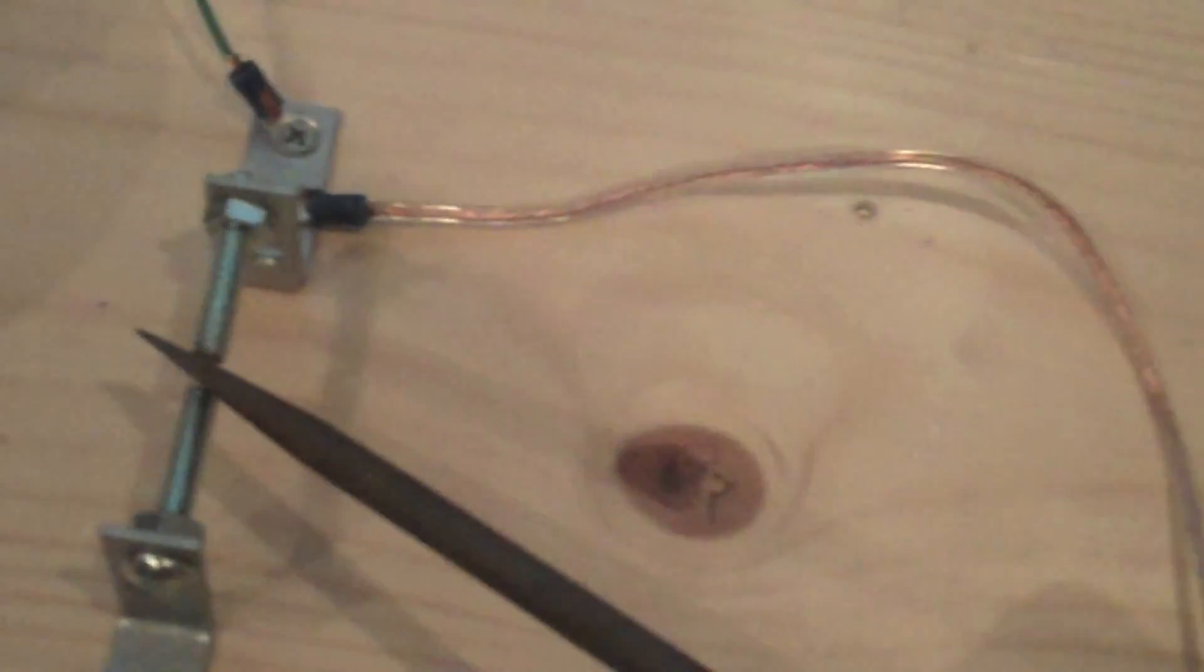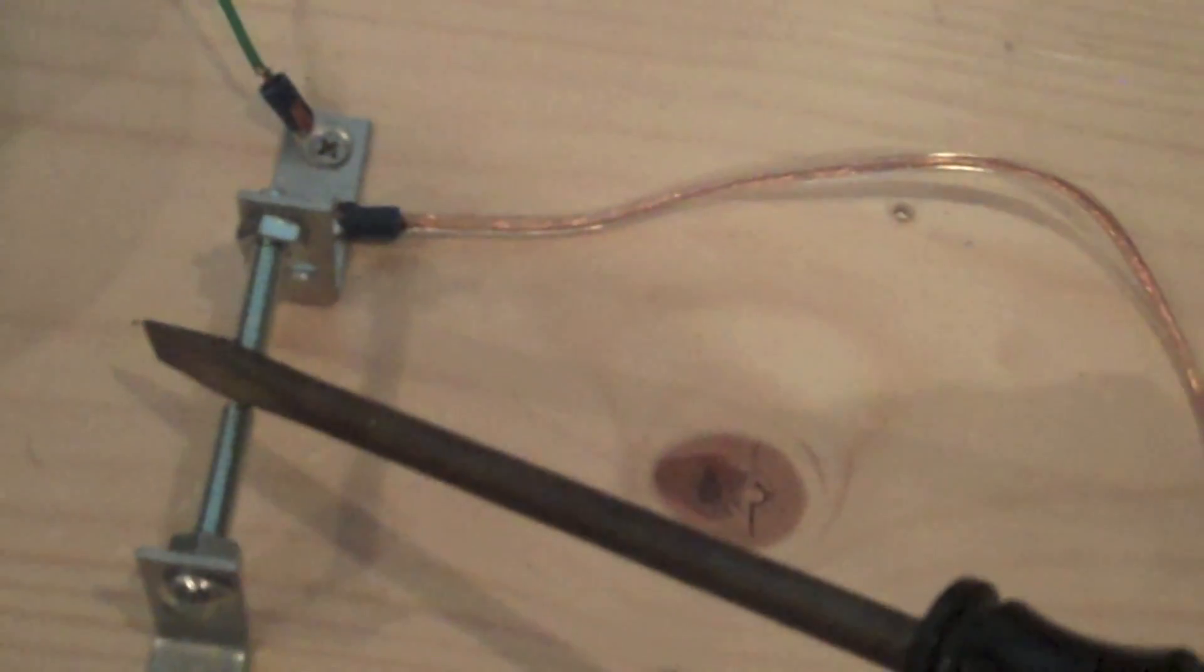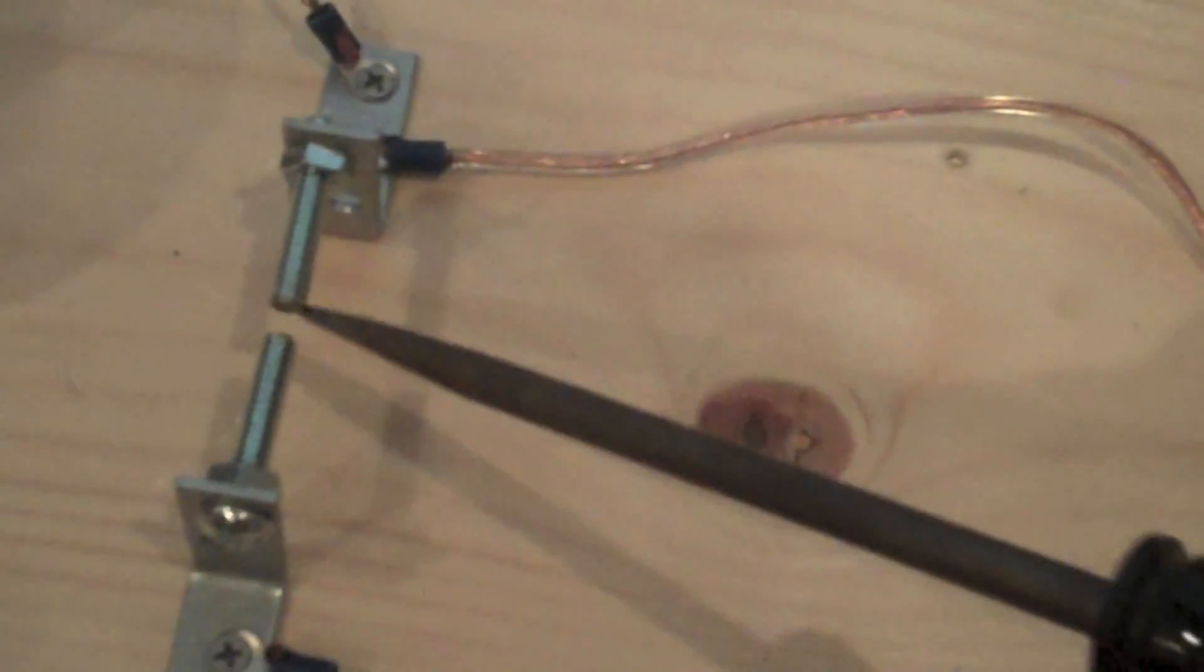But if you were here you'd probably be putting your hands on your ears. Now I'm going to discharge the capacitors, or short them, by putting a metal object that is insulated for me between the spark gap electrodes. Do this because they may store a charge, and if you discharge it or short it out, you'll be safe.